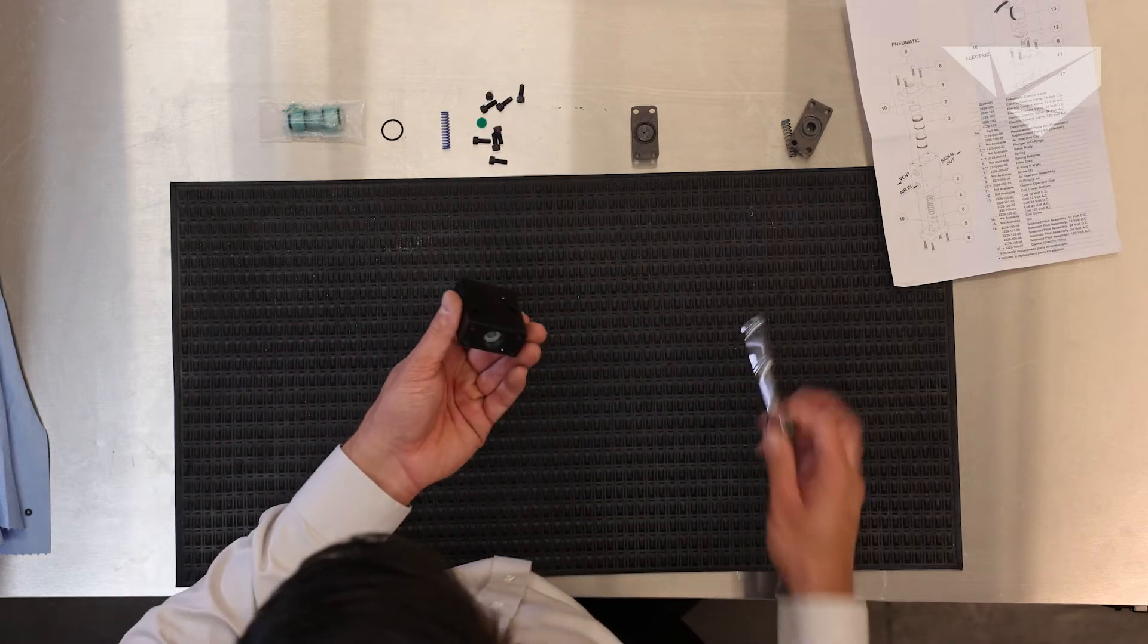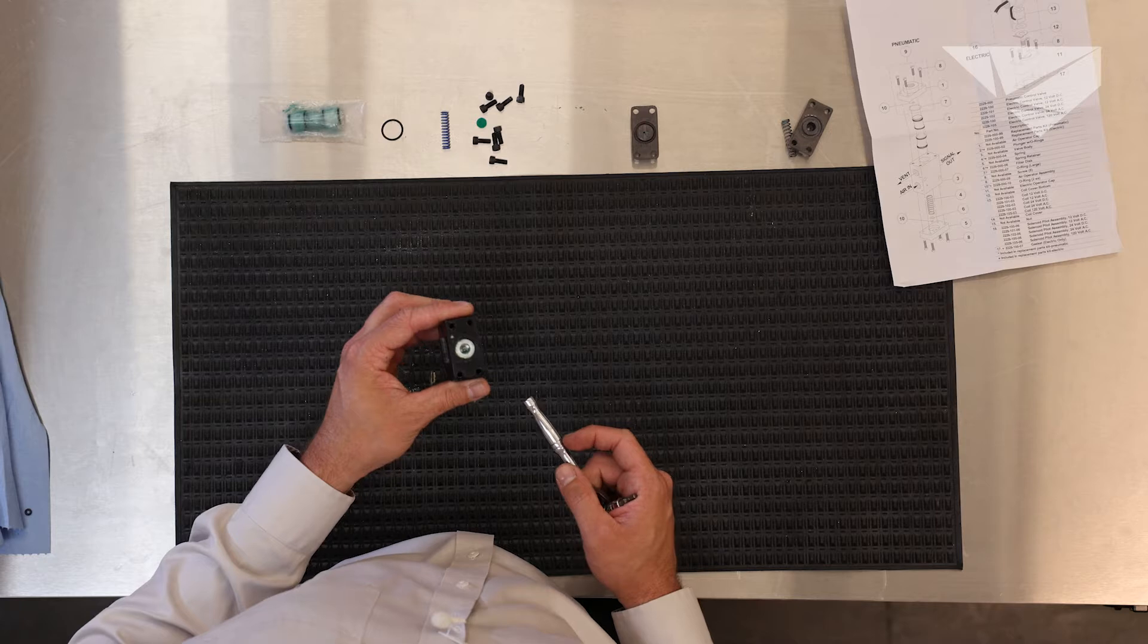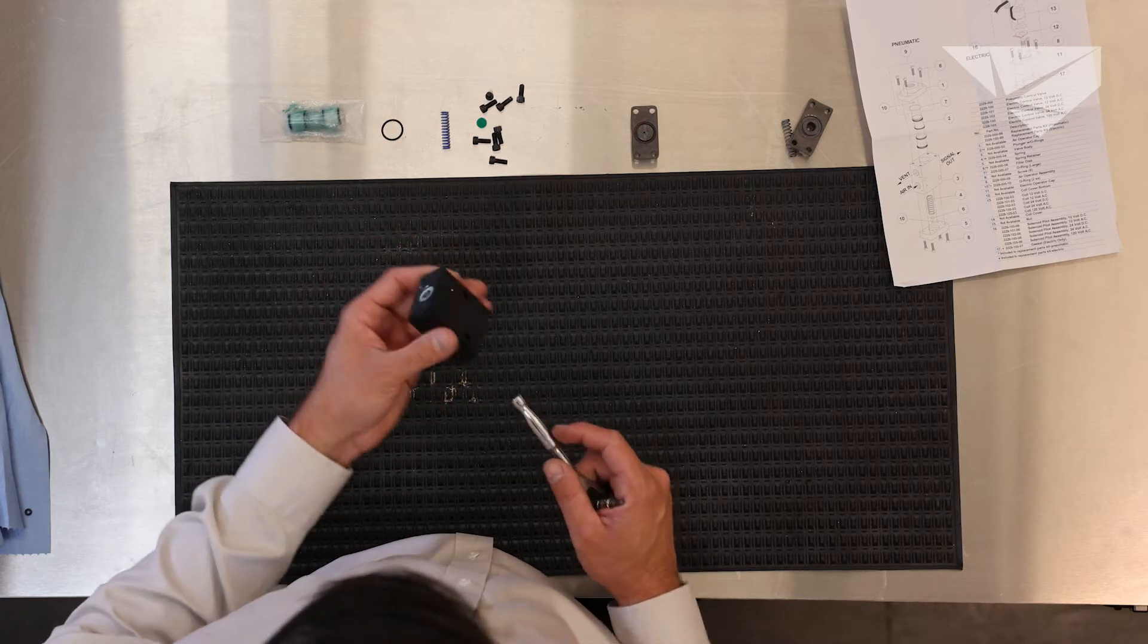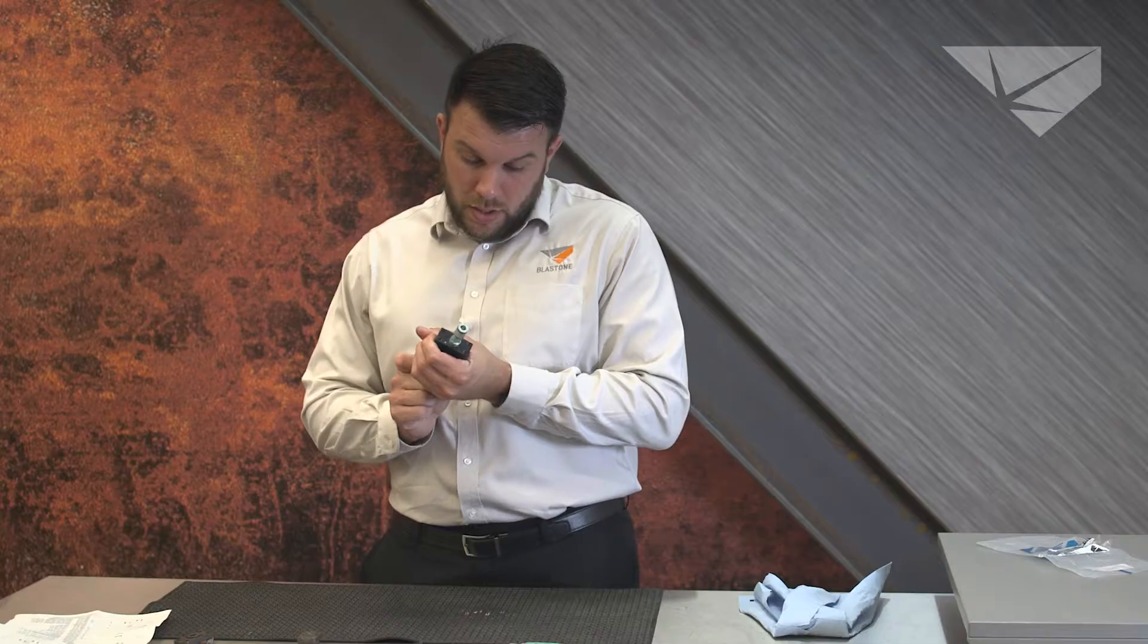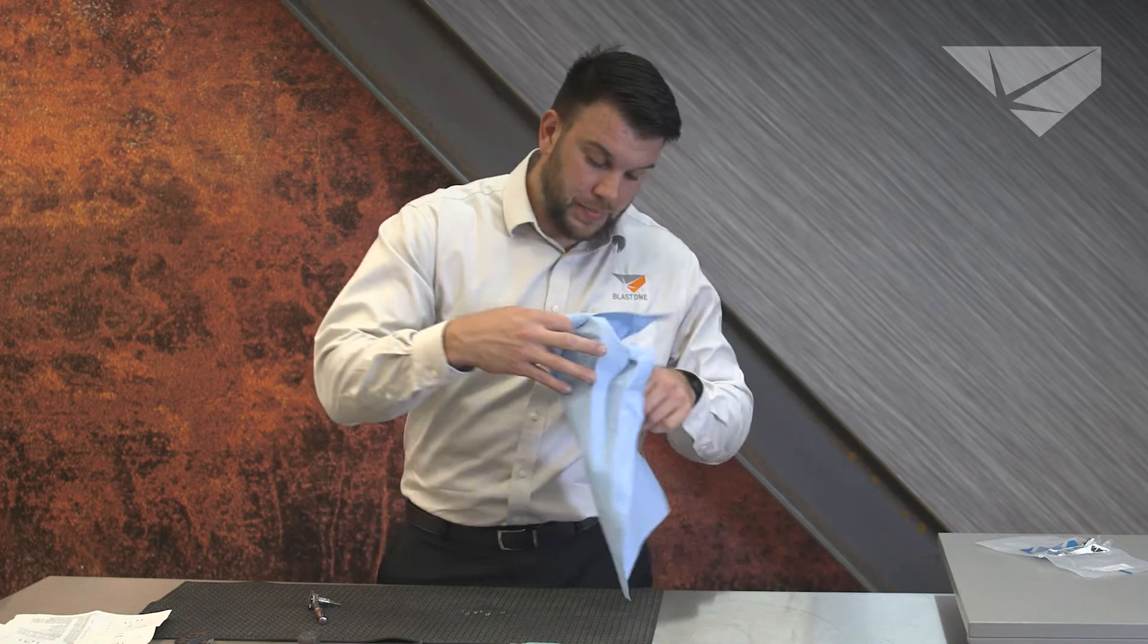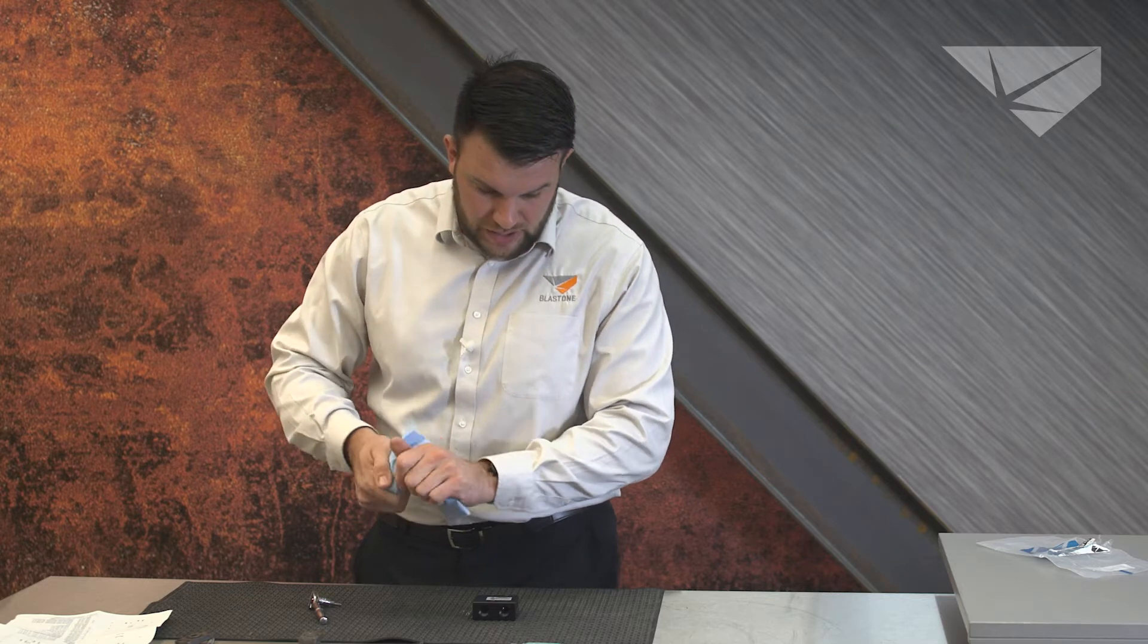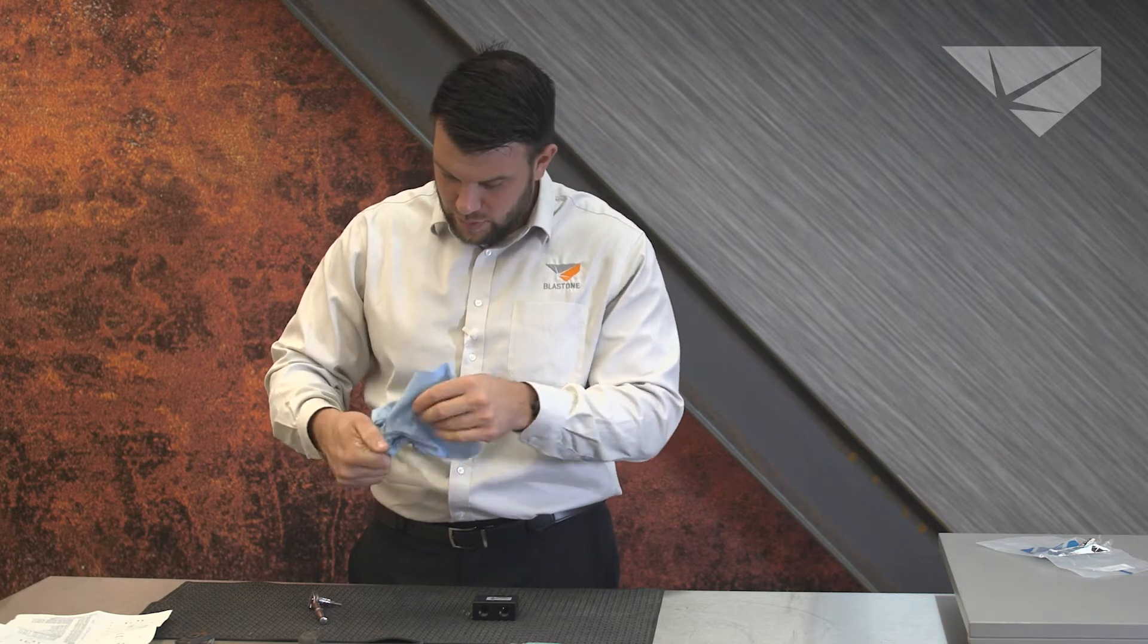And what you will see is the piston. Typically there is an aluminum piston or plastic piston. I prefer the plastic one because when abrasive gets stuck on the piston, the aluminum tends to seize up where the plastic one will just embed the abrasive and keep continuing to move.